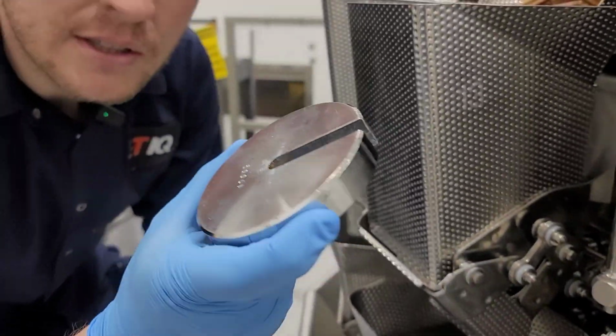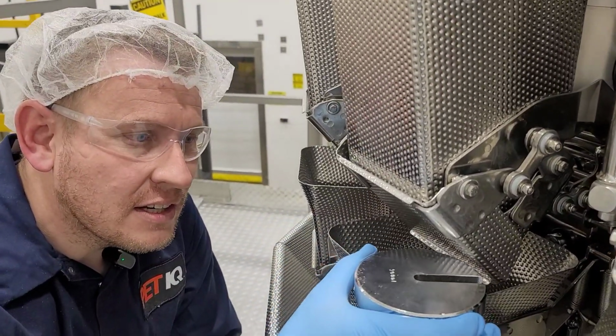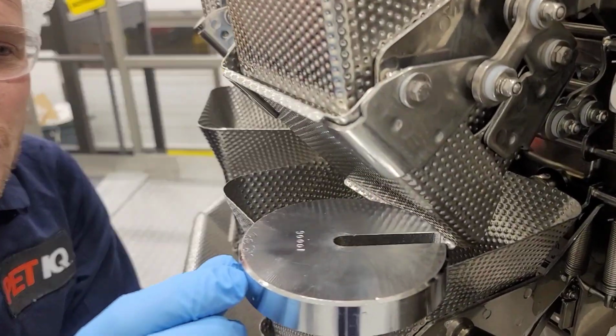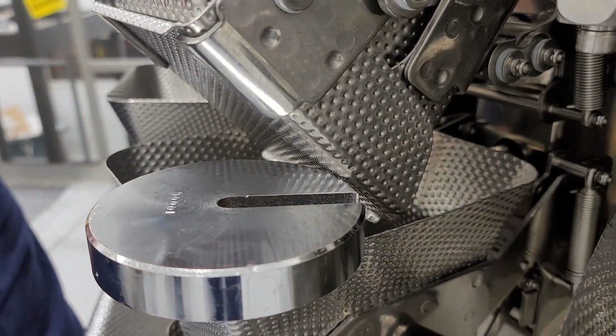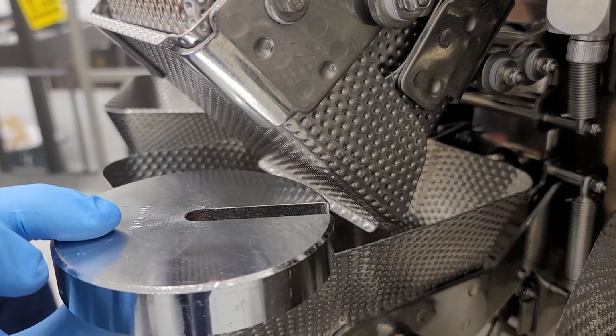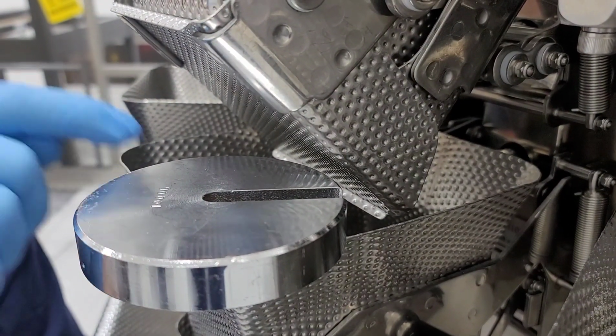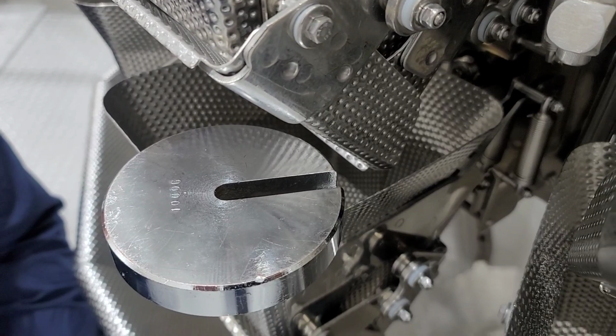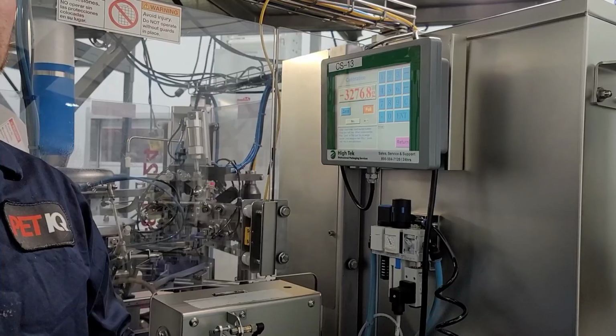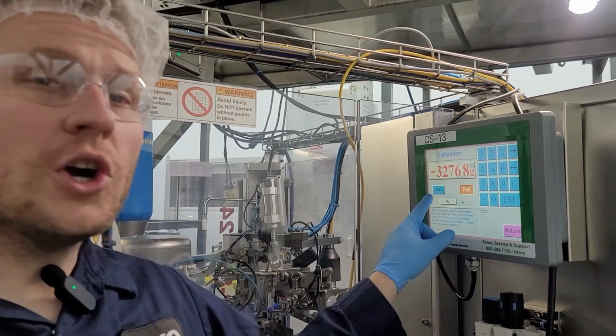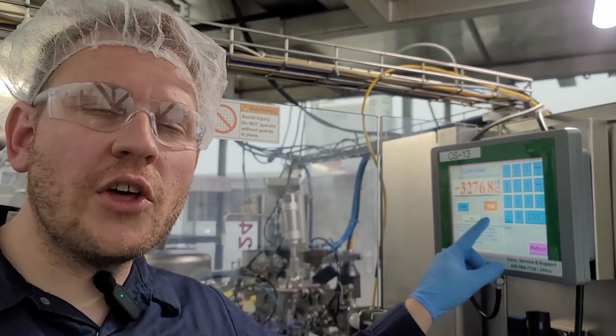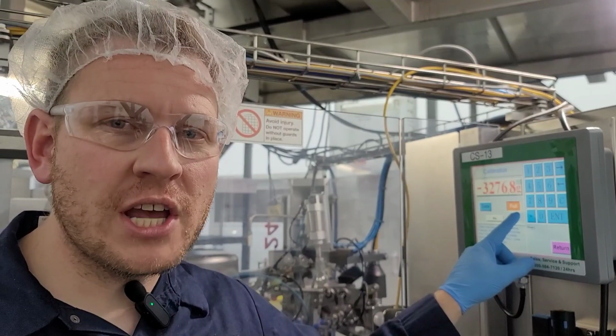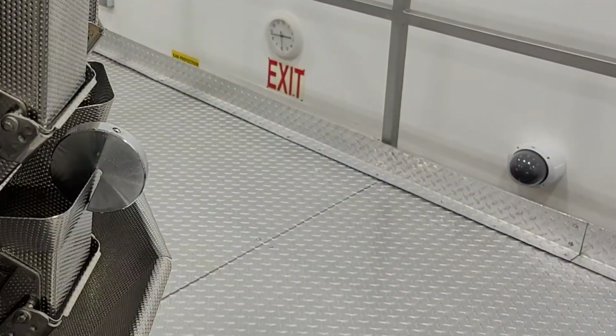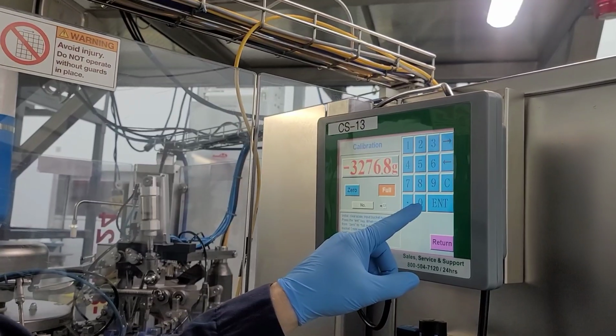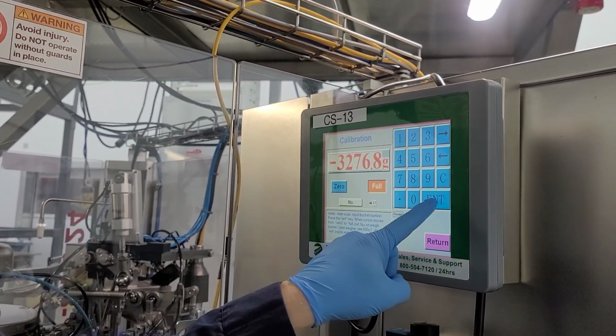It's important when placing the weight that the weight does not touch the top bucket. We don't want this. For an accurate calibration, the weight needs to be independent on the weigh bucket. When the cursor is moved to full, you can now tell the other technician to put the weight on the load cell. Put the weight on number 13. Once the weight is on and the technician has said the weight is there, press enter again.